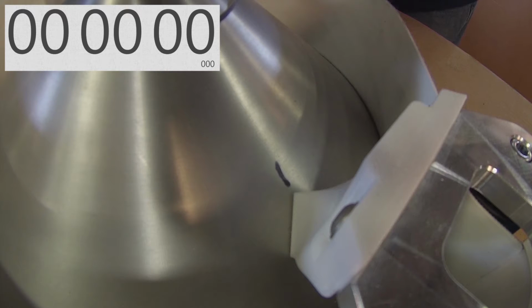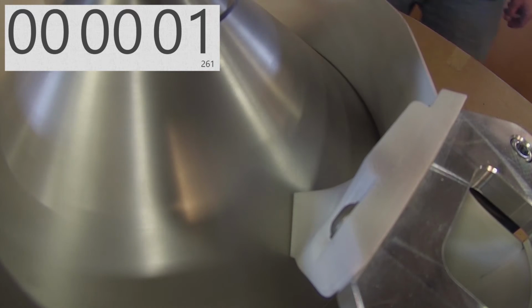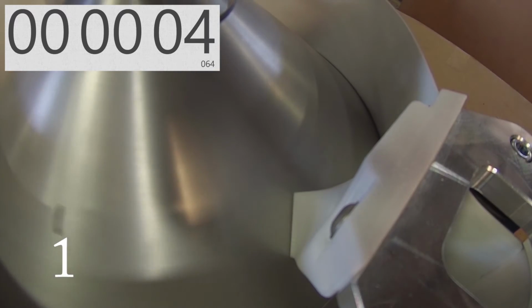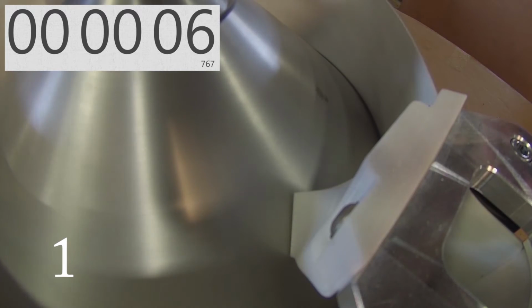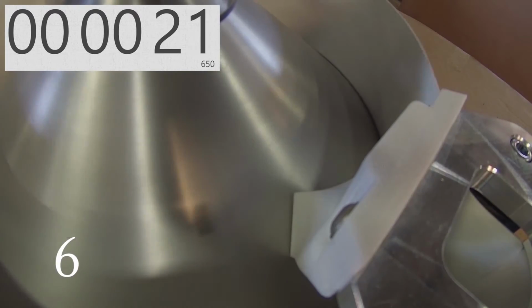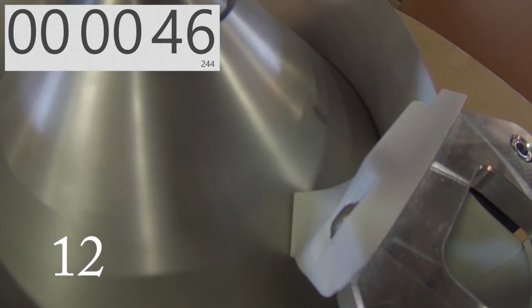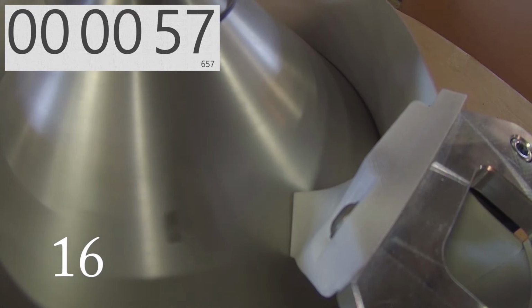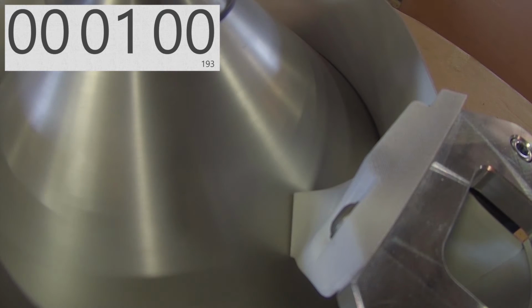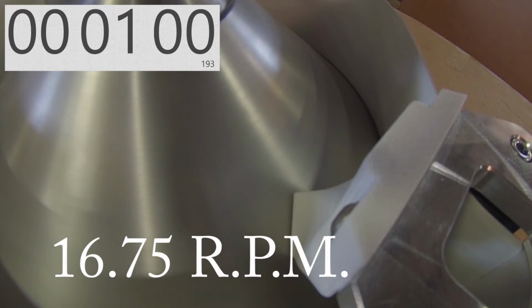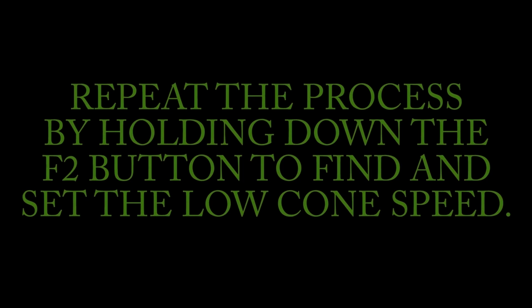Then we'll press the F1, the high cone speed, and hold that down for 1 minute. And then we just count the revolutions of the cone in that 1 minute time. When the cone stops spinning after 1 minute, we find out exactly how many RPMs the cone is spinning, and we enter this value into the PLC for our high cone speed. Then we'll repeat this process by holding down the F2 button for 1 minute and get the low cone speed and enter that into the PLC.